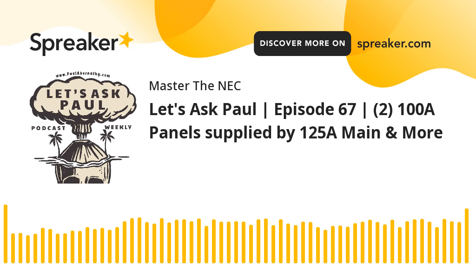So if the 100 amp breakers that are in there, you still have that 125 amp main, and you have these two 100s. Ultimately, you've got to remember that breaker in the main panel is there to protect that bus, right? And so even if I have the two 100 amps in there, the conductors are sized. You're protecting the conductors because he says they're sized properly. They're protected at 100 amps, or they have a rating for 100 amps, or at least can handle that. And then, of course, you have the breaker that's going to protect those conductors. That's what it's for. And then in those remote distribution panels, you have your different loads, and you're going to have branch circuit overcurrent protection, and it's going to be sized to protect those loads.